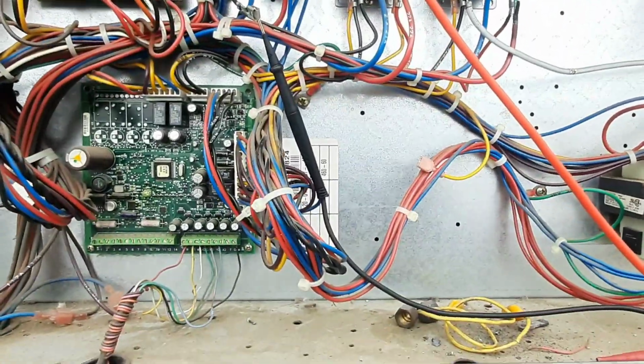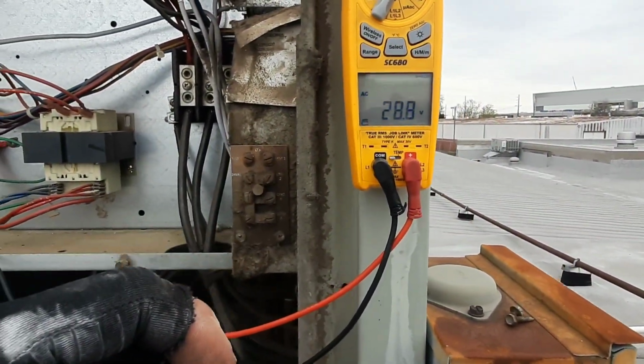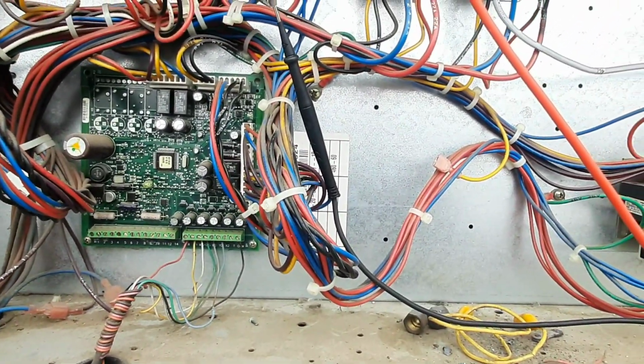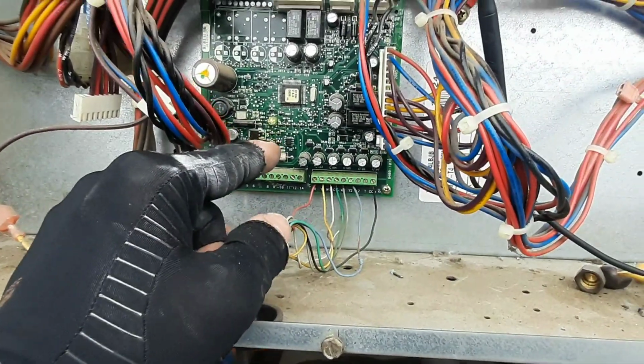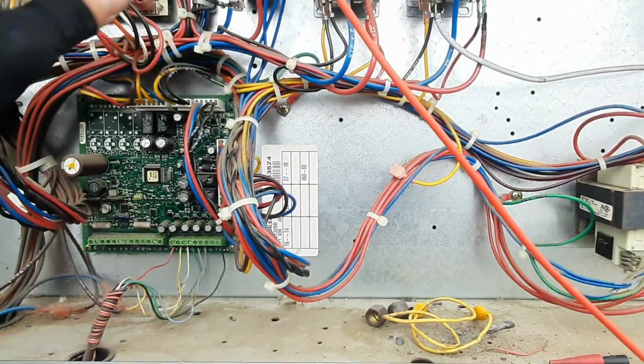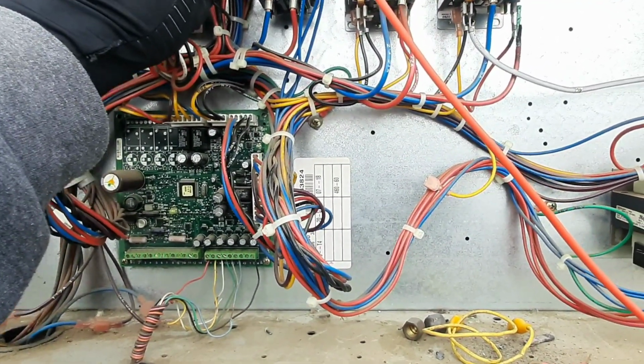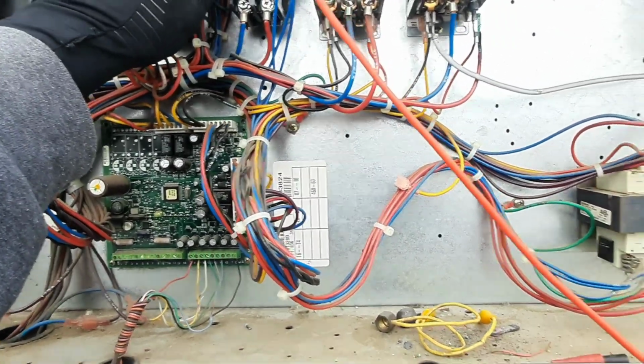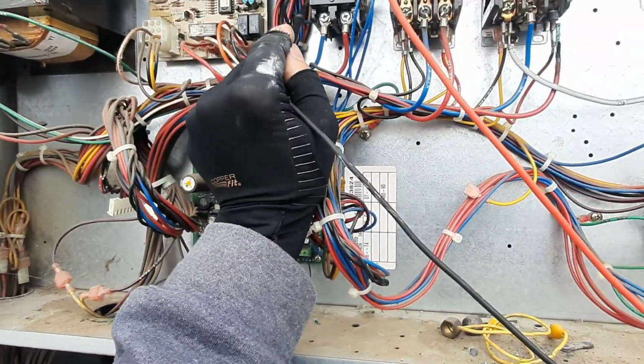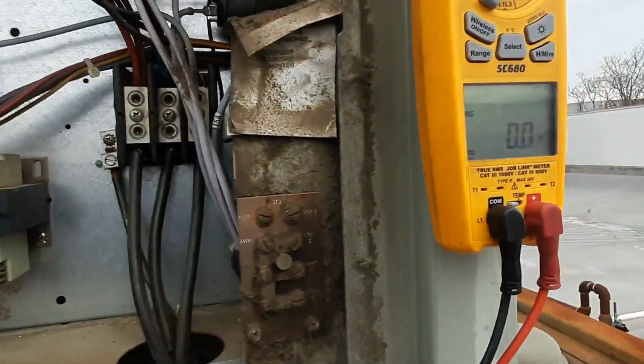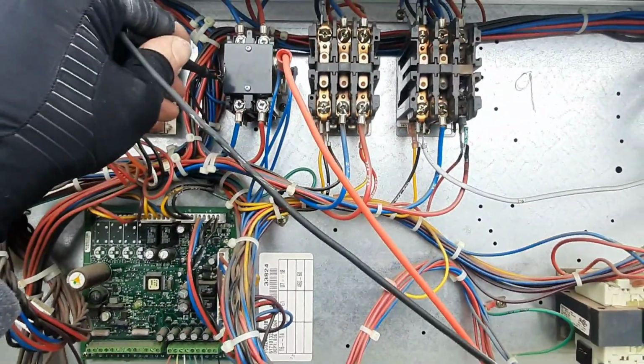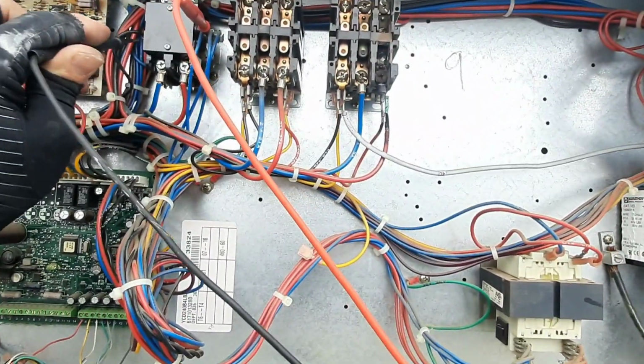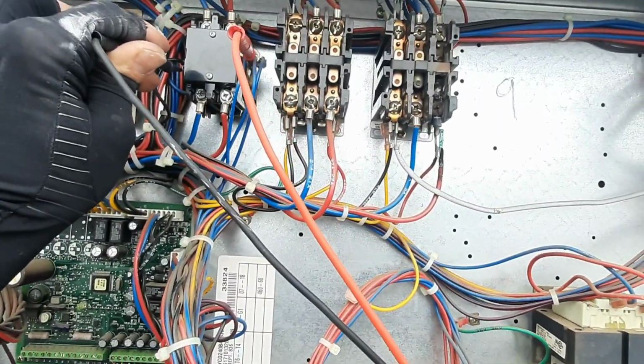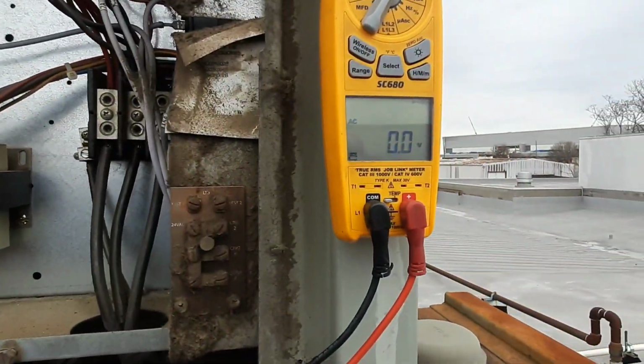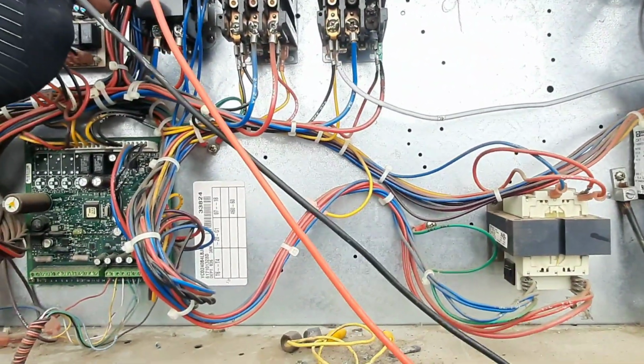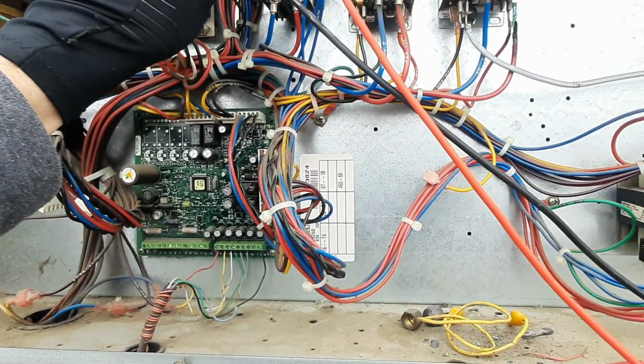So I got something wrong with our contactor. Might still have something wrong with the board because I just kicked it back on. My code's gone. You know what? Trane uses a triac, so I might not actually have. Gotta check it with it on. Because of how they do the triac, it's gotta be connected to actually read that voltage. Don't ask me to explain it. I've seen it a million times and still haven't been able to really wrap my brain around it, but it's not going to do it now.